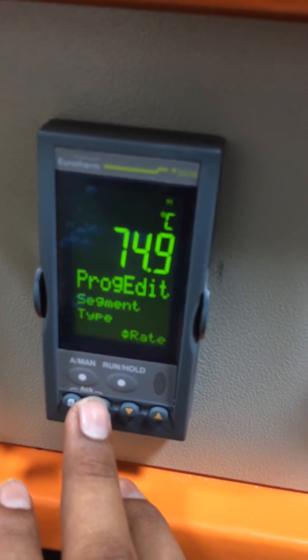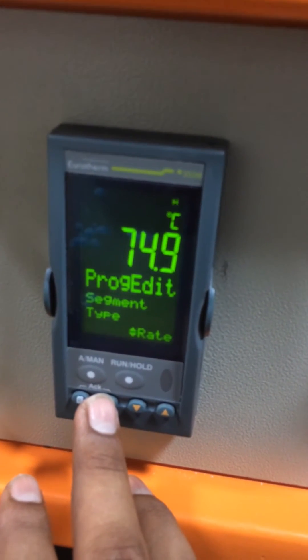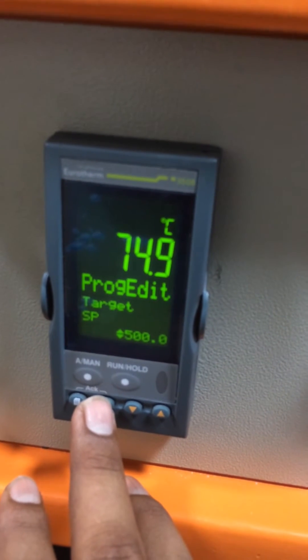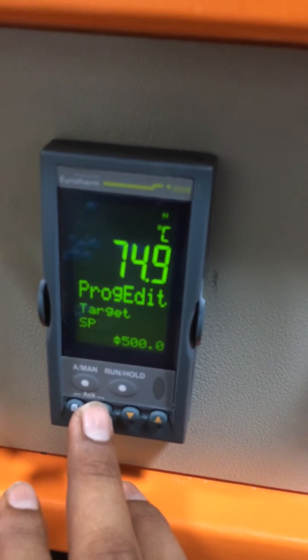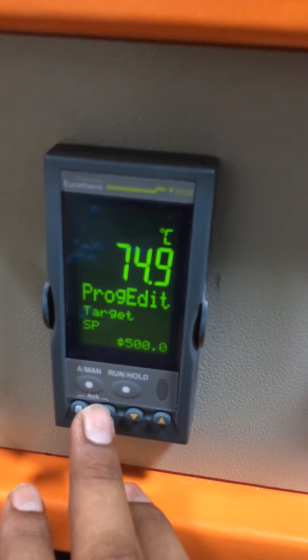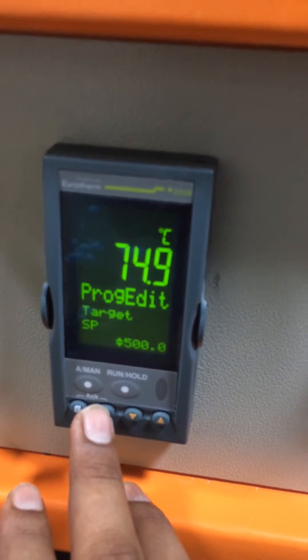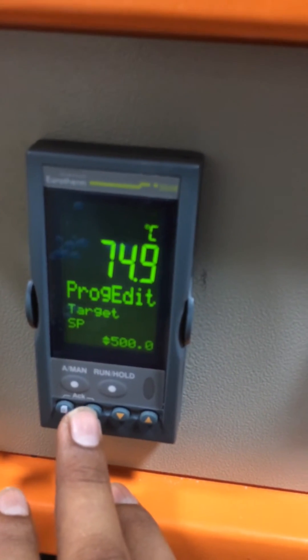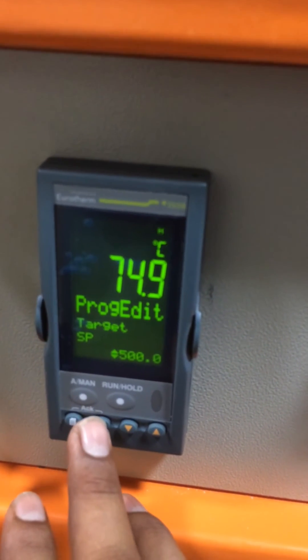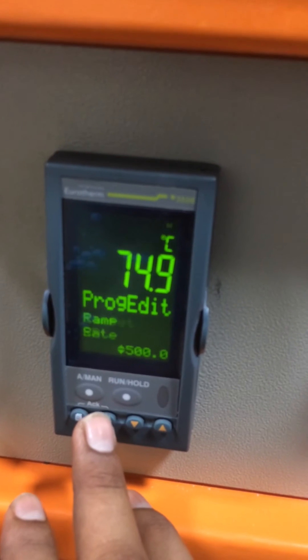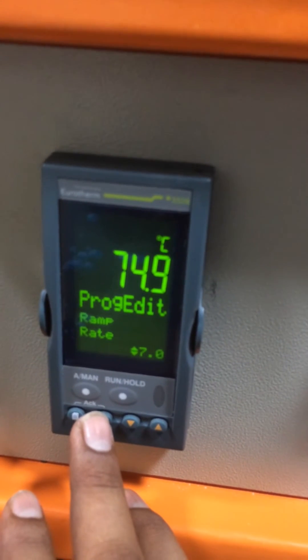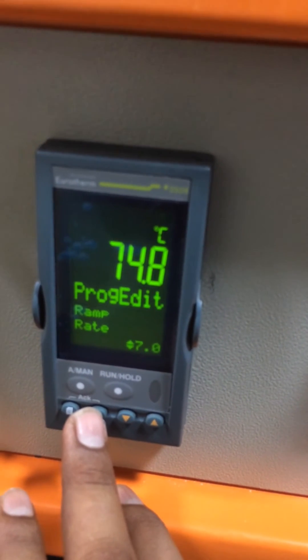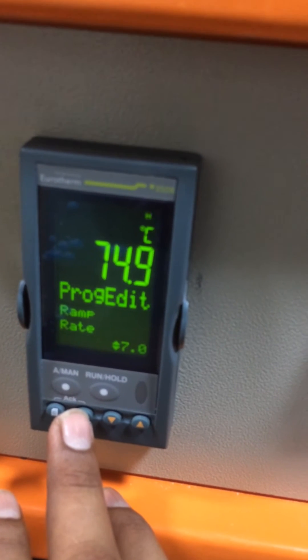Program segment type shows 'heating rate.' Target SP shows 500, meaning 500 degrees — you can increase the temperature here. The heating rate is set to 7 degrees per minute ramp rate, which you can increase or decrease. Then press enter again.